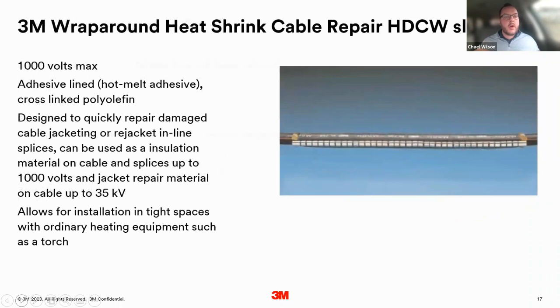And then the last one here is our 3M wraparound heat shrink cable repair. This is a really good product if you don't have access to the end of the cable, but you need to put your heat shrink on. You can just wrap it around. It's essentially a zipper on the edge that you zip closed, and then you heat shrink as normal. So really good if you don't have access to the end of the cable. It can get you out of a sticky situation. A lot of the time, it saves a lot of time rather than shutting everything down, detaching it, and putting standard heat shrink over the end of the cable.